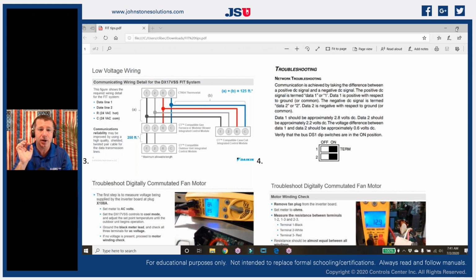So if I go from ground to number 1 and, in this example, I've got 2.8 volts DC, and then I go from ground to number 2 and I have a negative 2.2 volts DC, well, I subtract the two of those and I've got a 0.6 difference. That is my bias. So what I'm looking for is a 0.6 volts DC bias or greater. If I have less than 0.6 volts DC, my system can't communicate properly.